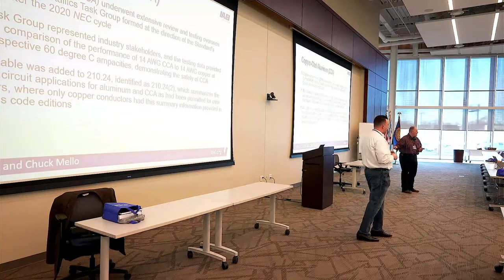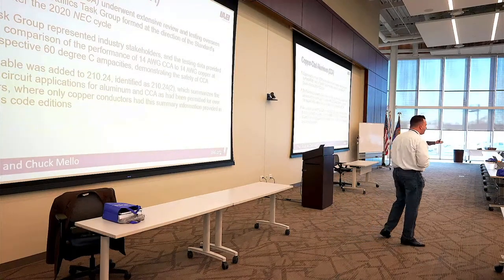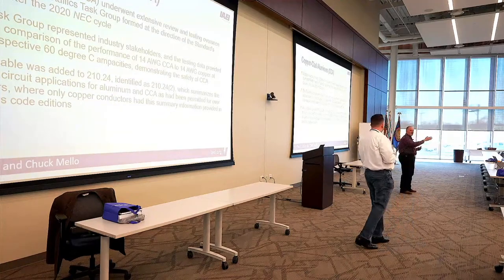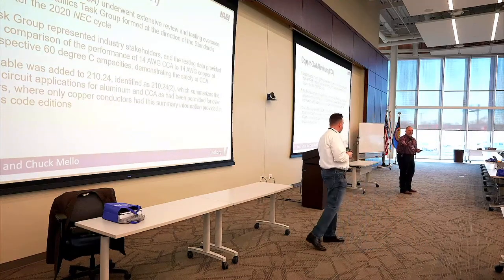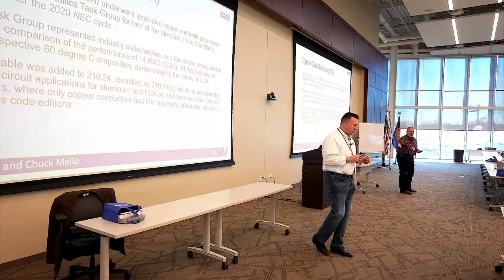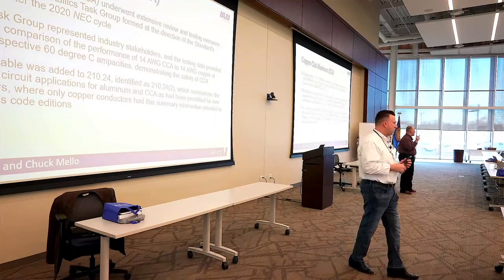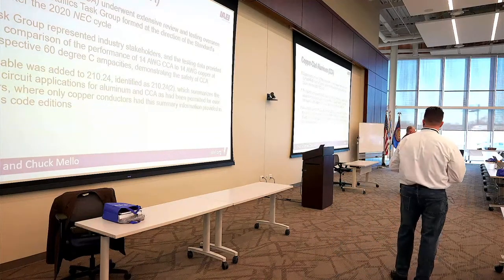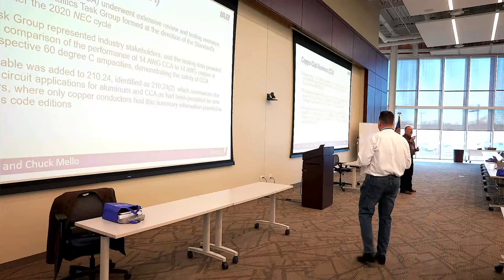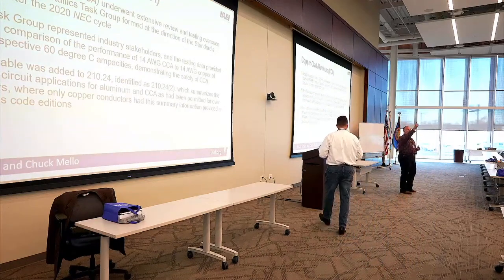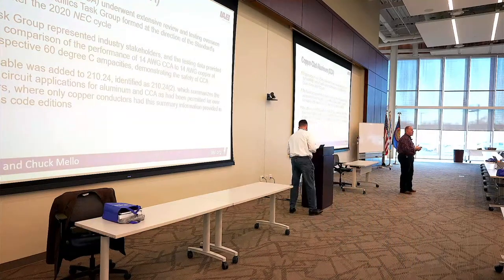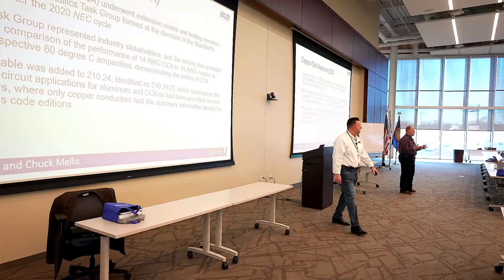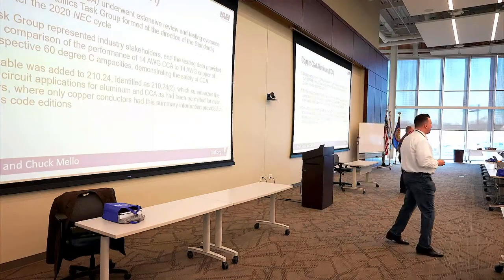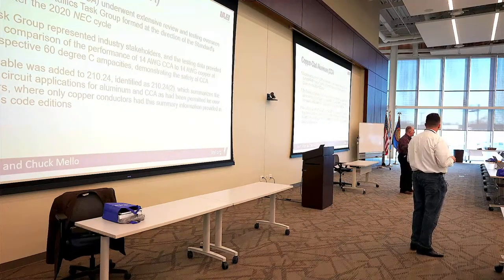I got a 15 amp receptacle, I got 20 amp, and you all know the rules on what you can put on a 15, what you can put on a 20, 30, etcetera. So we don't have a 10 amp receptacle. So we said, look, we can't permit you to put it on receptacles. We can permit it to be used on lighting. Think about what we're doing in lighting - we're going to LED lighting, much lower current draw. You can go with smaller conductors, go a longer way, right?